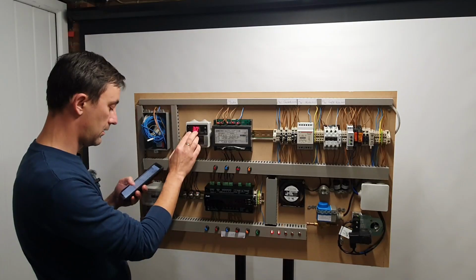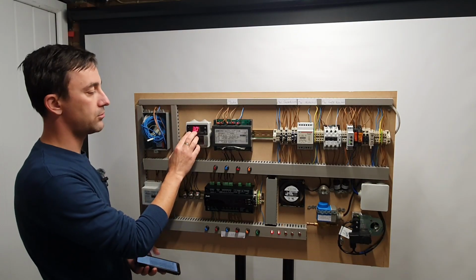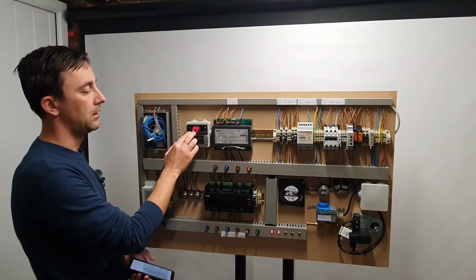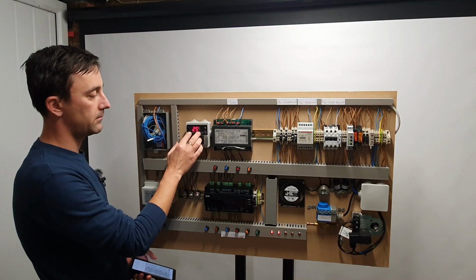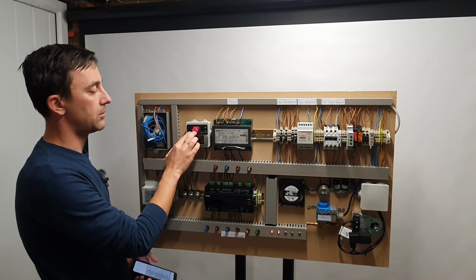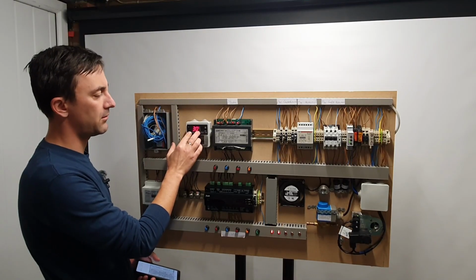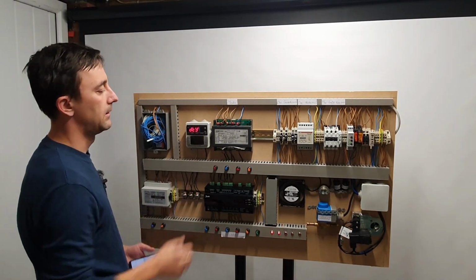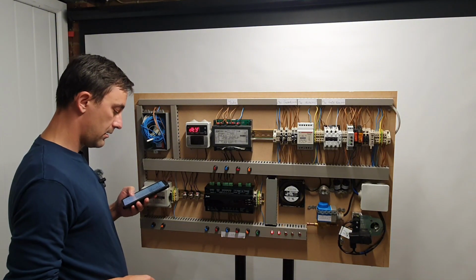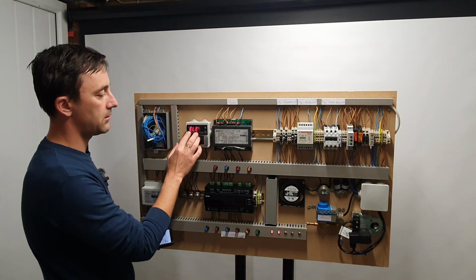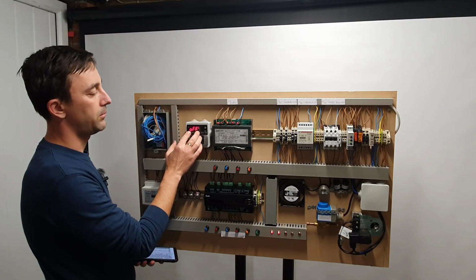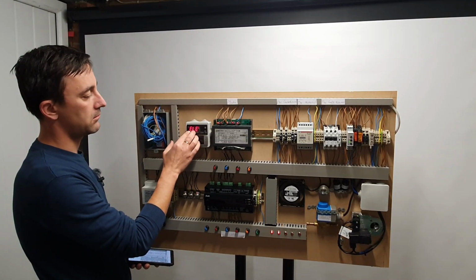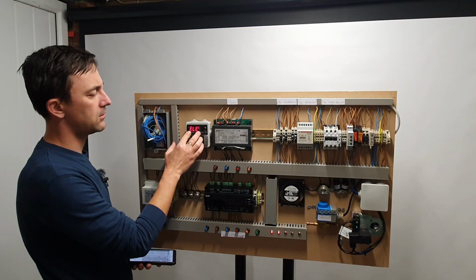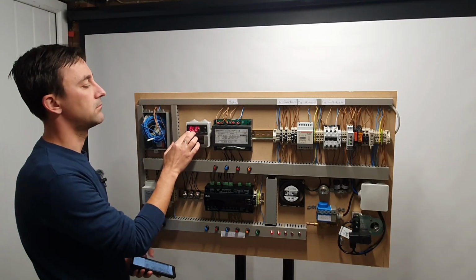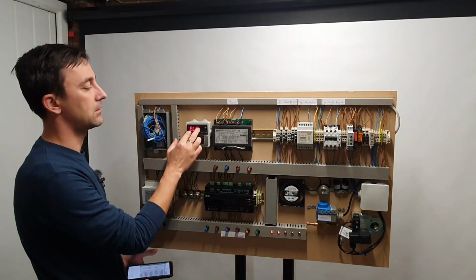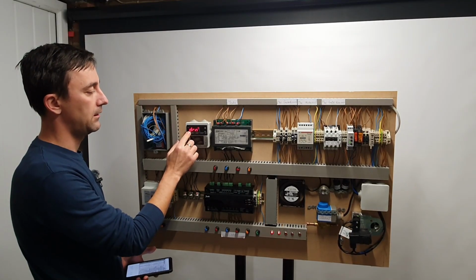DTO is maximum defrost duration, 30 minutes. Sometimes it can be 25, and it can range actually between 25 minutes and 45 minutes. But I think 30 minutes should be enough. DTY is defrost type. Well, if it's a freezer, it should be electric. The options are off cycle, electric, or hot gas. This one's got an electric heater, so we're gonna tell the controller that.